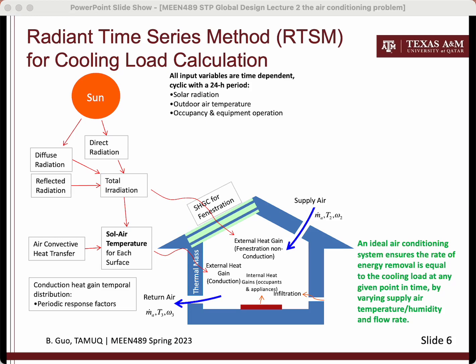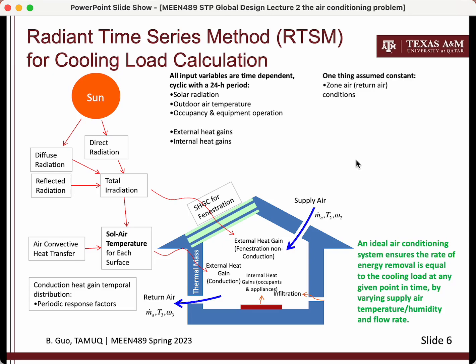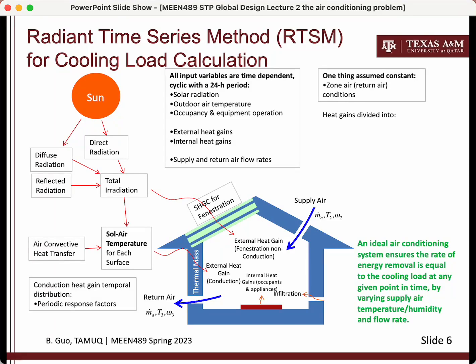The design conditions for the air conditioning problem include outside weather conditions including solar radiation, and the building's occupancy and operating schedule. The zone air or return air condition is a fixed condition selected by the designer. The designer uses these input conditions to determine the heat gains, which are further divided into radiative and convective as well as sensible and latent. Latent heat gain is always convective. The designer usually also needs to determine the ventilation rate — the flow rate of fresh air — though this may be unnecessary for a small shelter with a high rate of infiltration.